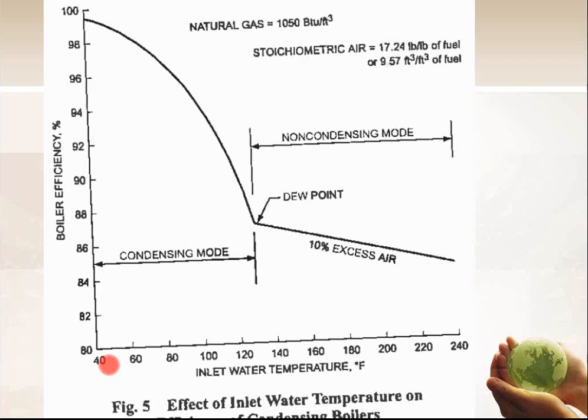Radiant floors, loves it. If you've got snow melt or radiant floors, there's no reason not to put a condensing boiler in. Even if you bought a new boiler last week and it's a cast iron one, throw it away and get a condensing boiler. The payback is going to be dramatically quick.